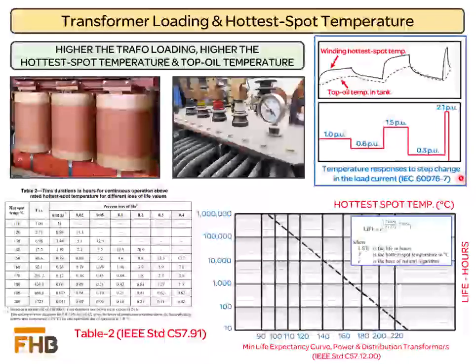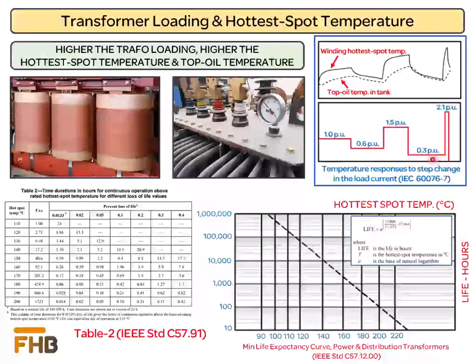IEC standard 60076-7 defines how the operating temperature of the transformer increases and decreases with the transformer loading. Since the oil temperature is dependent on the winding temperature, the values of the oil temperature are always lower than the winding temperature. Winding temperature of the transformer is measured by installing temperature sensors in the transformer winding. It is common to measure the transformer top oil temperature through a thermometer installed at the top cover of the transformer.